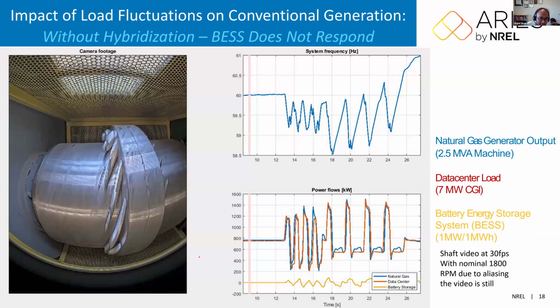Here is one video I would like to play, where the blue line is the natural gas generator output. We configured that 2.5 MW synchronous machine as natural gas because we are using an industrial controller, the governor control, so the mode selected was natural gas. The red or orange is emulated load from one of our grid simulators, varying between 200 kilowatts and 1400 kilowatts.